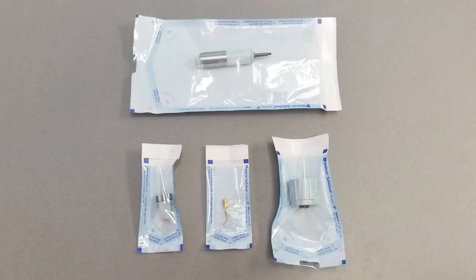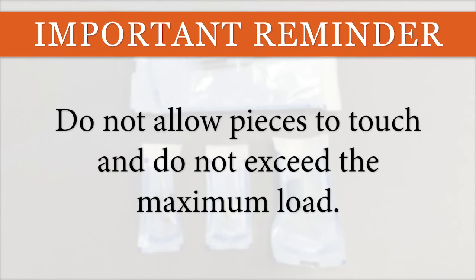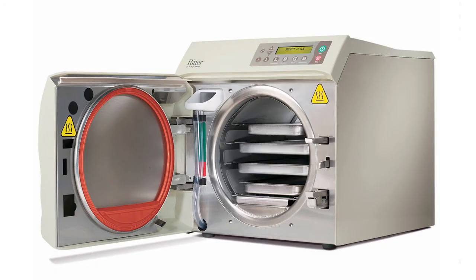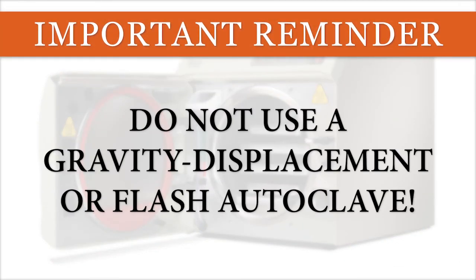All accessories should be sterilized individually using a single-use medical steam sterilization pouch of the appropriate size. Do not allow pieces to touch when sterilizing multiple instruments in a cycle, and ensure that the maximum load is not exceeded. Sterilization of components requires a pre-vacuum steam autoclave. Do not use a gravity displacement or flash autoclave.